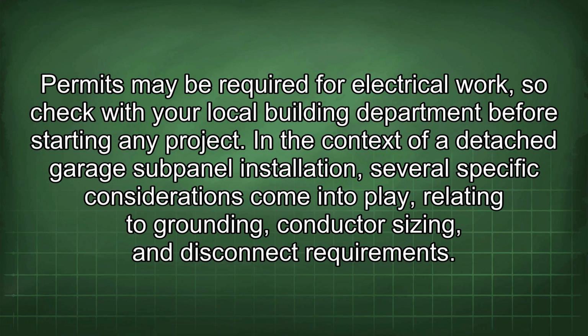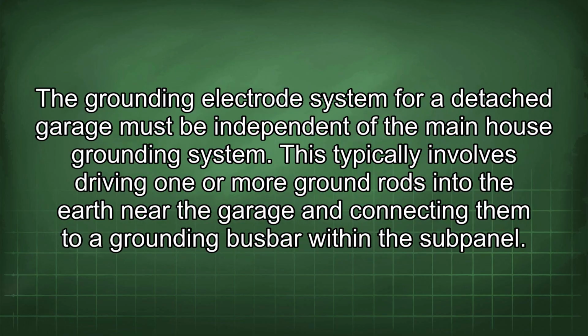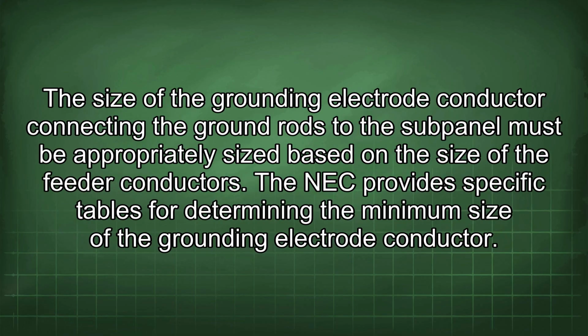In the context of a detached garage subpanel installation, several specific considerations come into play relating to grounding, conductor sizing, and disconnect requirements. The grounding electrode system for a detached garage must be independent of the main house grounding system. This typically involves driving one or more ground rods into the earth near the garage and connecting them to a grounding busbar within the subpanel. The size of the grounding electrode conductor connecting the ground rods to the subpanel must be appropriately sized based on the size of the feeder conductors. The NEC provides specific tables for determining the minimum size of the grounding electrode conductor.